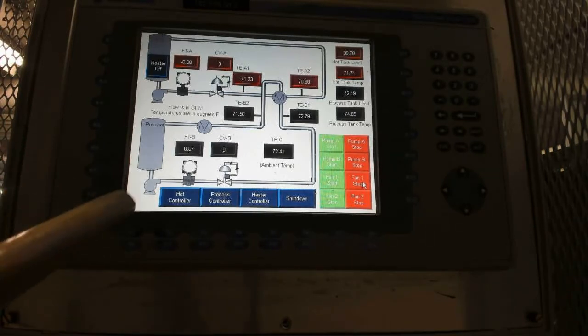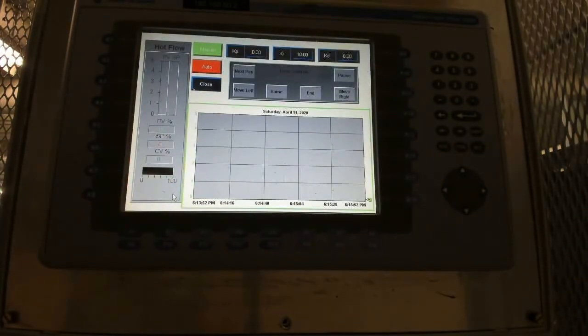Then we can go into our heat transfer, our hot controller. In here we can set up for automatic mode, we can put it for manual mode, and we have what's called tuning constants across the top here. So these are our tuning constants. This is how the system would perform in automatic mode. In an automated mode, we're using a PID, proportional integral derivative control scheme, and these are those parameters. And then if you want to run it in manual mode, you can actually set the flow rate, and you can see this is hot flow.